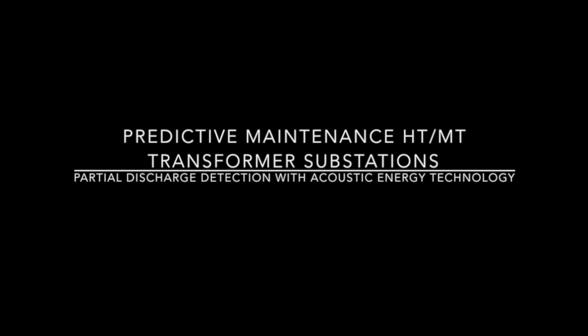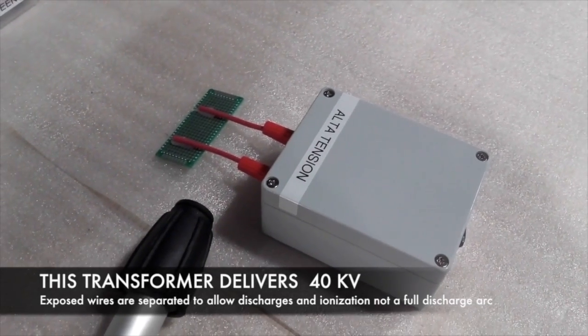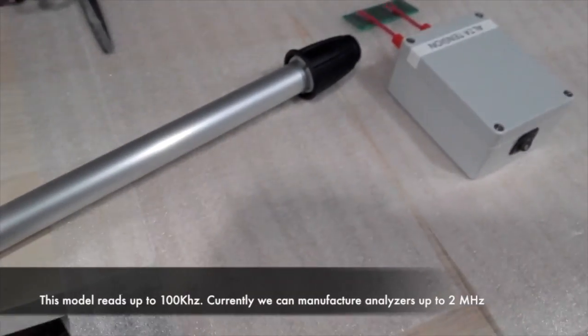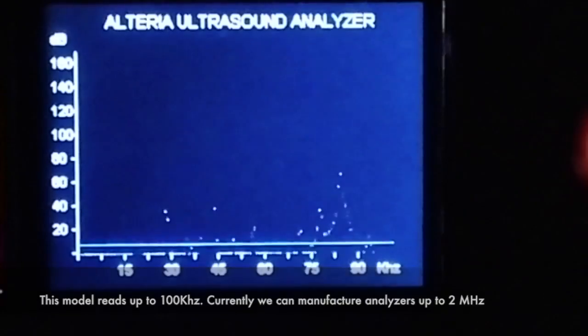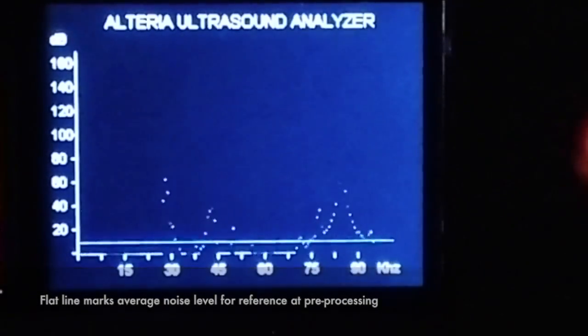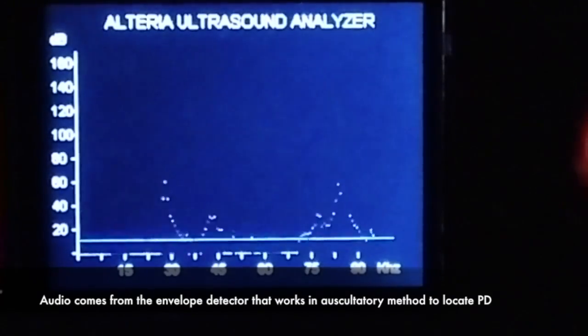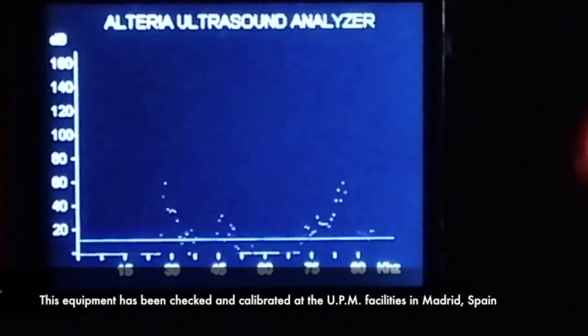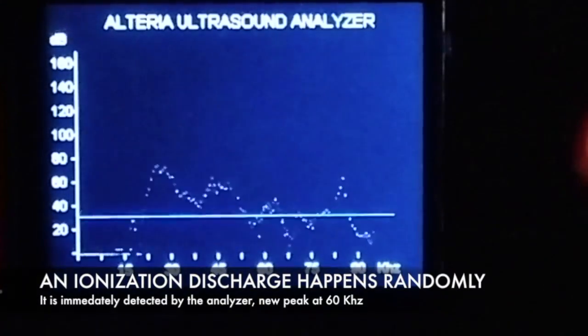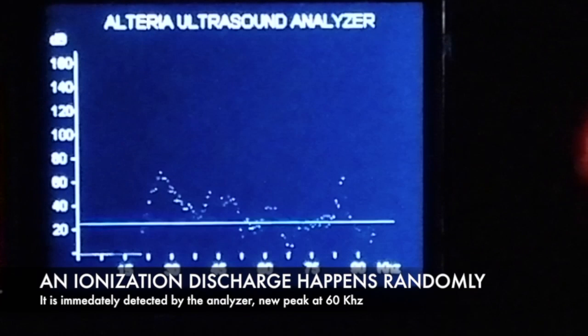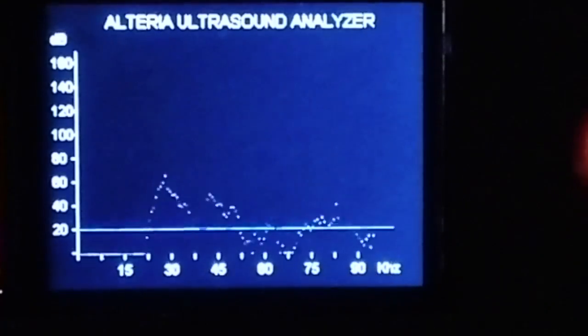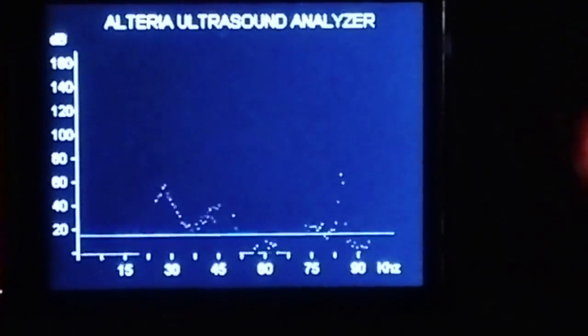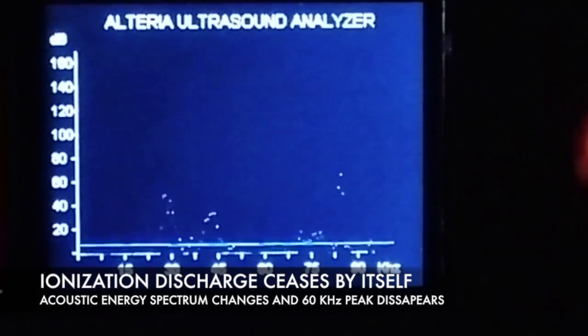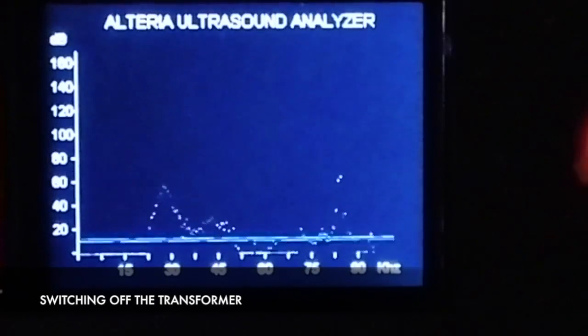And now we are showing a video clip regarding the use of ultrasound sensors in substation transformer predictive maintenance for medium and high voltage applications. Okay, this is a medium voltage transformer that delivers 40 kilovolts, and you are seeing the spectrum that here is basically ultrasound acoustic energy from 30 kilohertz to 80 something kilohertz, and here you are seeing that ionization discharge happen and vanishes after that. The spectrum goes back smoothly to the normal one.